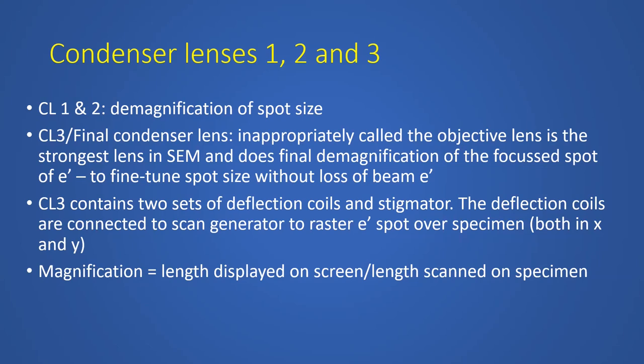And that's the kind of spot size that you want. So the first two condenser lenses deal with the demagnification of the spot size. And CL3, as a final condenser, is used for the final demagnification of the focal spot to fine-tune the spot size without the loss of beam electrons. This is inappropriately called the objective lens, which is the strongest lens in the SEM and the most important one. That's why it's called the objective lens, but it's not correct actually.